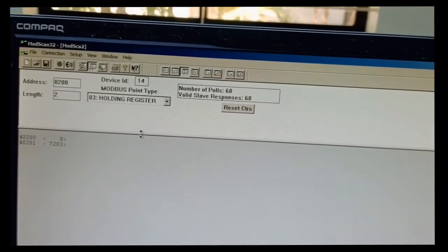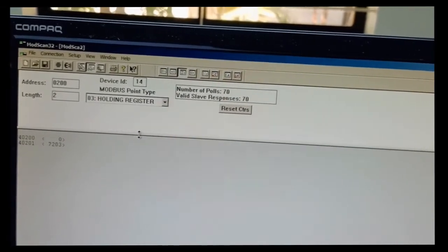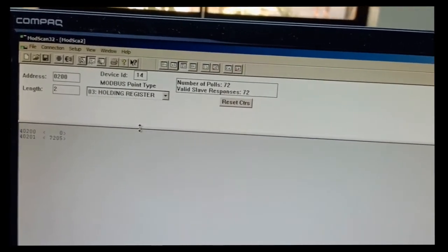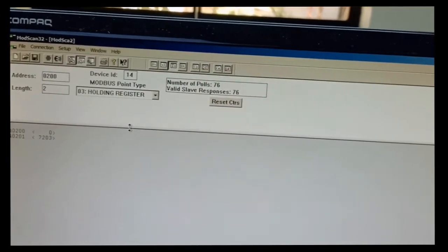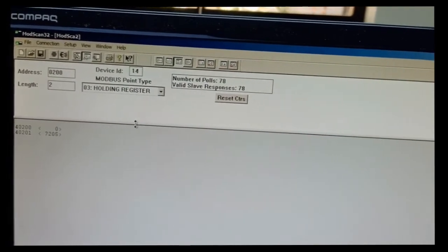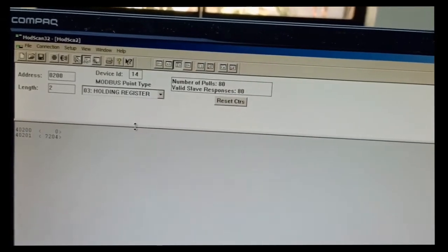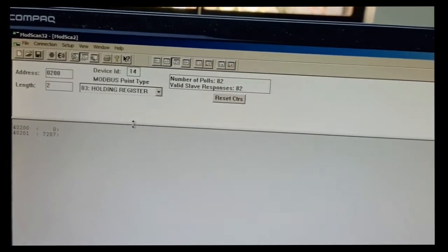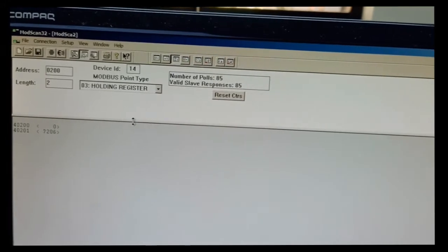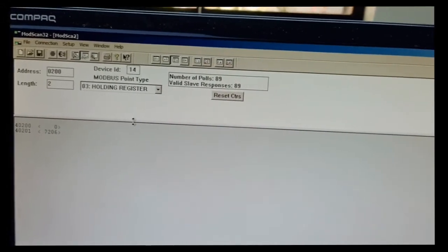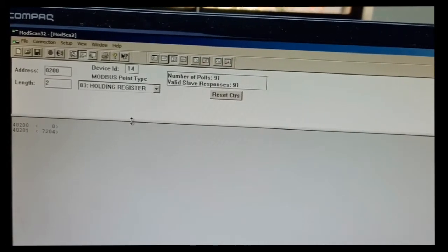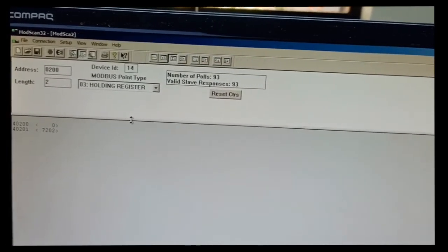The higher 2 bytes come on address 200 and the lower 2 bytes come on 201. So we need to combine all 4 bytes and then read. This data is less than 2 bytes, that's why we are getting the correct reading on 201. As per the address map we need to divide this reading by 100, so we will get the same reading as per the meter display.